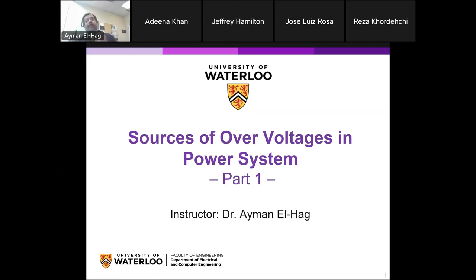Now, one important question is why we are testing the equipment at high voltages in our labs. For example, the transformer: we test it at high voltage AC, high voltage lightning impulse, and high voltage switching impulse. What is the reason, if the transformer will be connected to 11 kilovolt or 13.8 kilovolt? Why do I have to test it at 38 kilovolt AC and 95 kilovolt impulse? What was the reason for that?